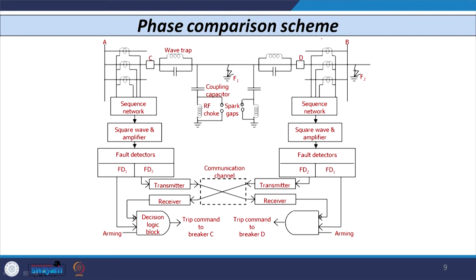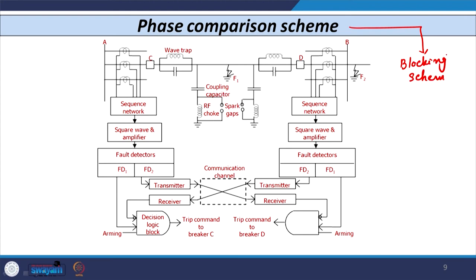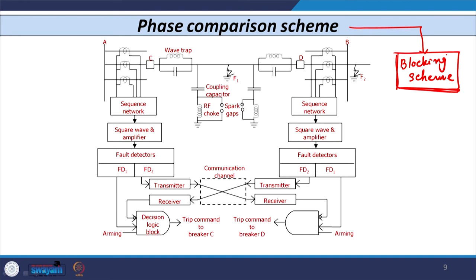Let us discuss the phase comparison scheme first. The phase comparison scheme compares the angle between the current entering and the current leaving the line. During normal conditions or external faults, the two currents are in phase — the phase difference is 0°. In case of an internal fault, the remote end current reverses, so the two currents are out of phase with a phase difference of 180°, and tripping is given. In the specific type shown here, the carrier signal is used as a blocking scheme.